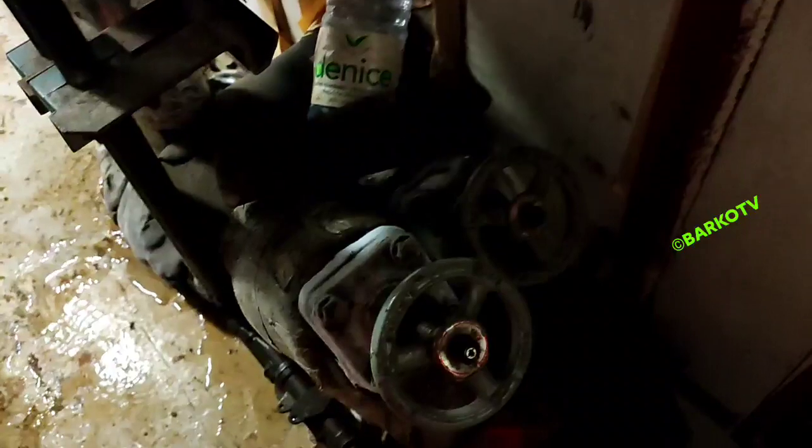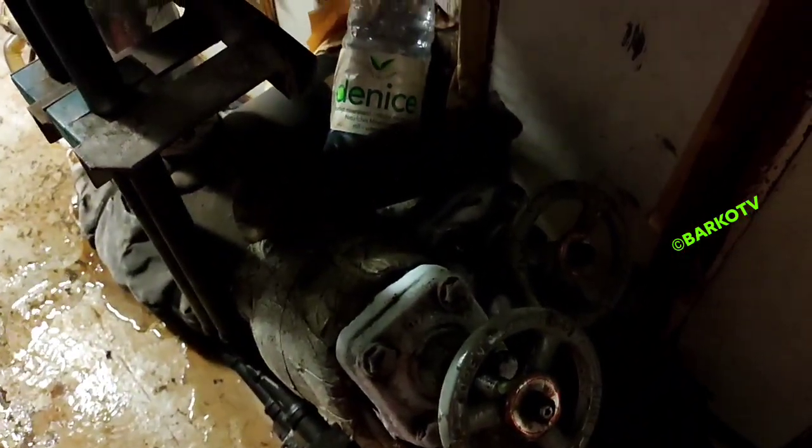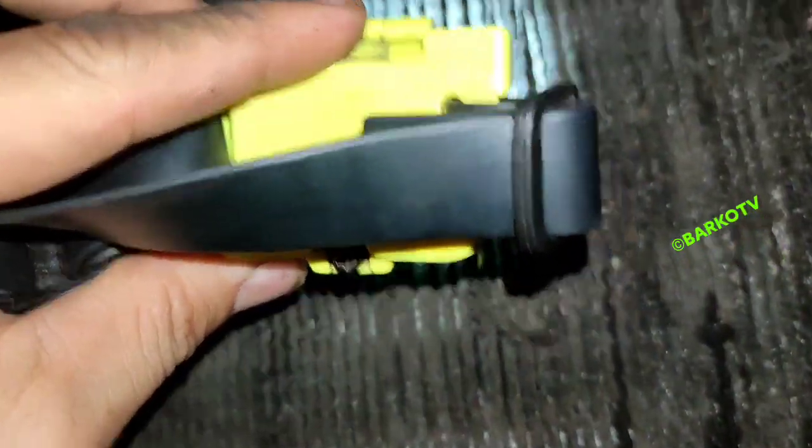We cannot cool down the accommodation at that temperature on the suction side. We need to clean this area. When removing the filter, I check the evaporator — without the filter, we can better inspect the evaporator condition directly.